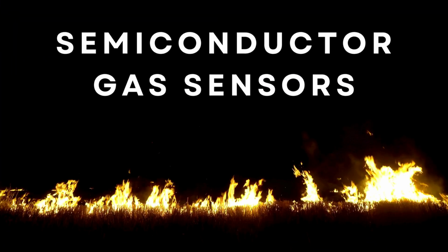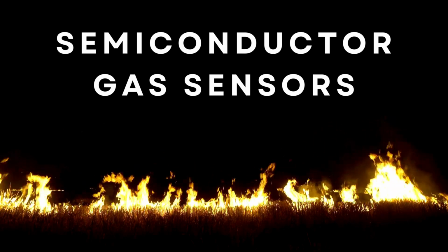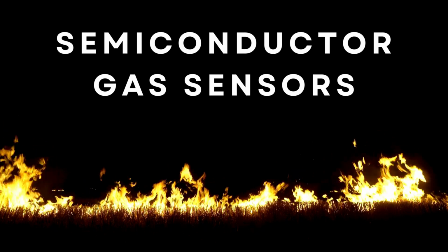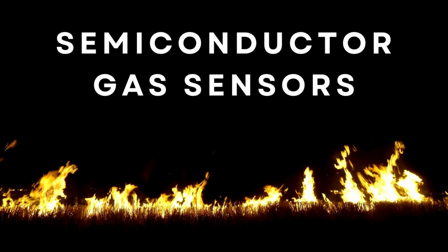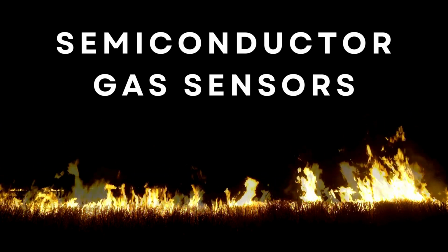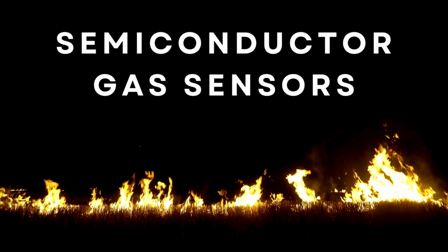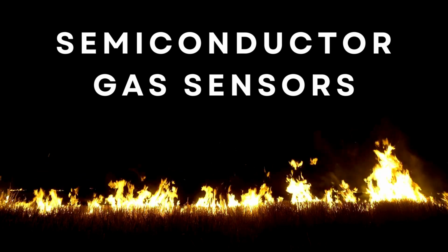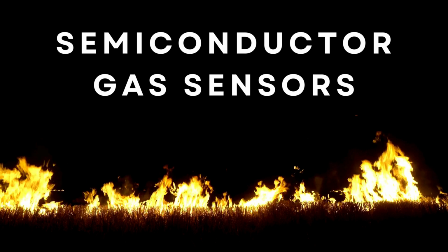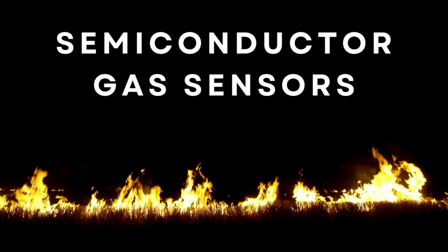Semiconductor sensors are based on changes in the electrical conductivity of a semiconductor material when gases come in contact with it. The semiconductor material is sandwiched between two electrodes and acts as a resistor. When the gas interacts with the semiconductor material, it changes its conductivity, resulting in a measurable change in electrical resistance.